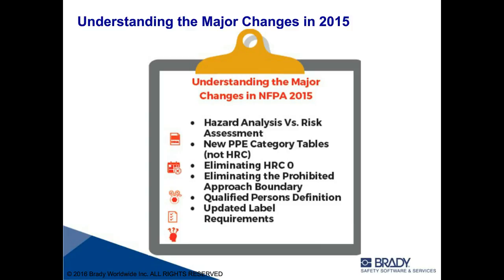Similarly, if you look at prohibited approach boundaries, they also removed that terminology. There used to be 3 approach boundaries. Prohibited was at 1 inch. The other 2, limited and restricted, drove some type of action on the user. Qualified people understood this, and as they approached the panel, those 2 boundaries made them do something—you couldn't allow unqualified people within, or you had to have your PPE on. The prohibited approach at 1 inch didn't cause any actions, so the authors of the code decided to get rid of it because it was causing some confusion.